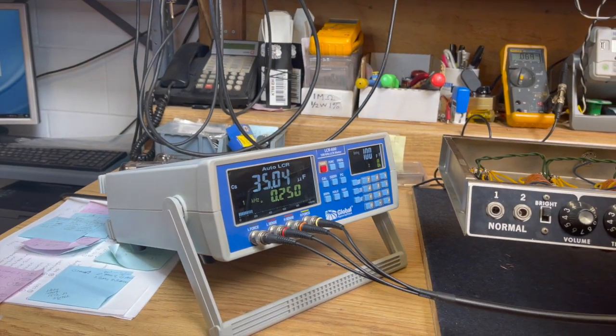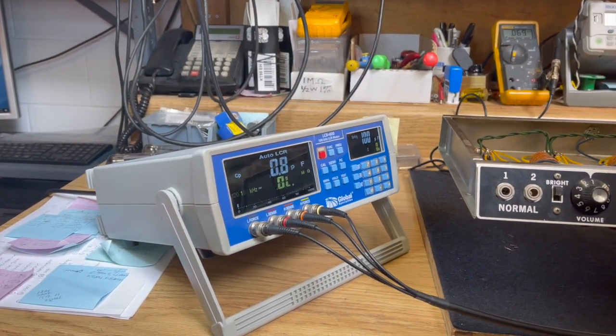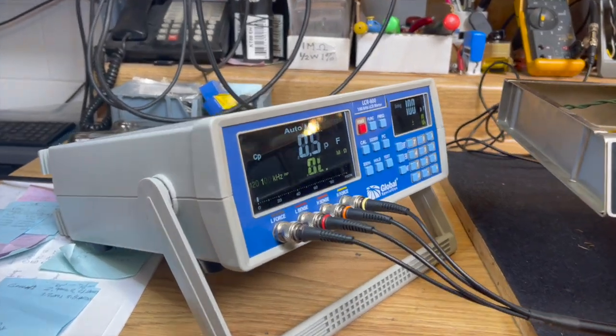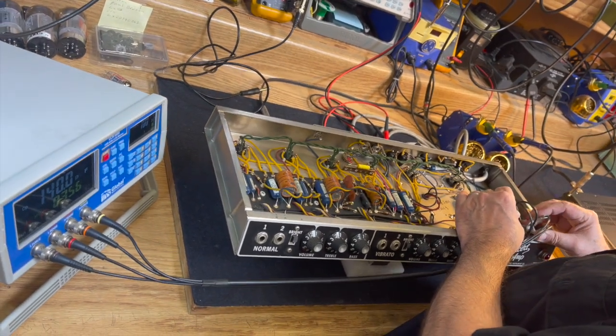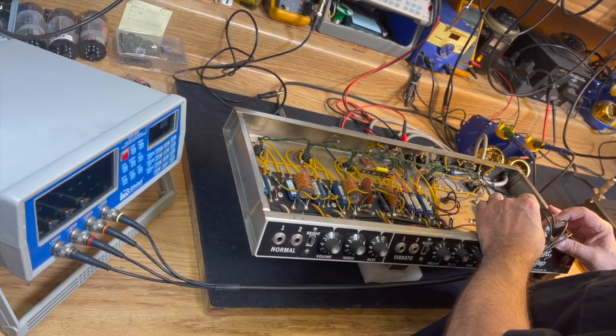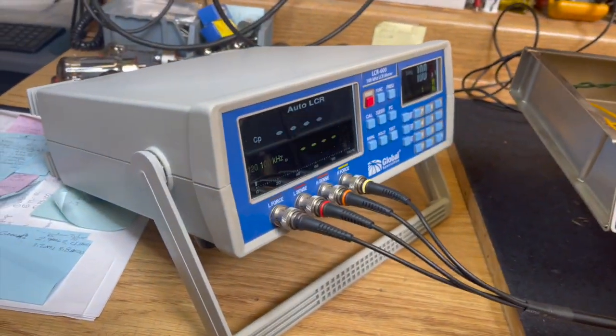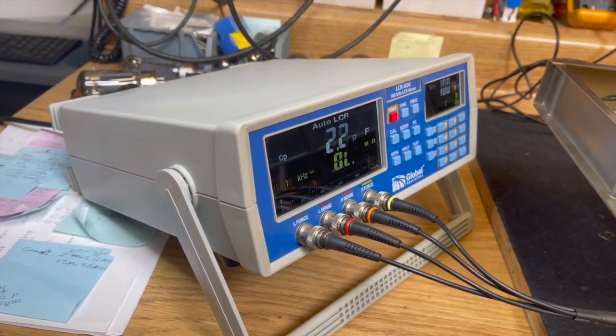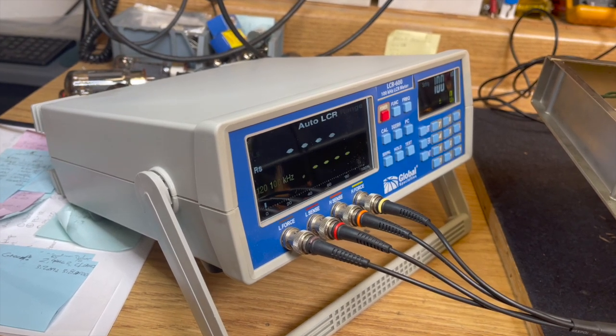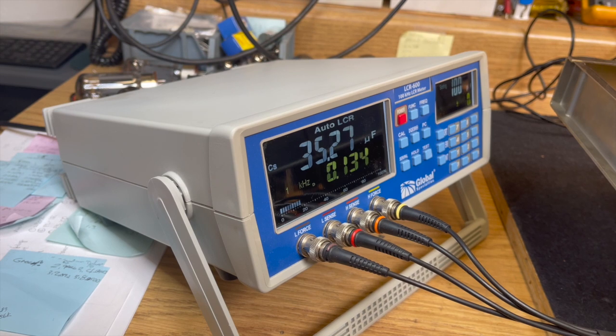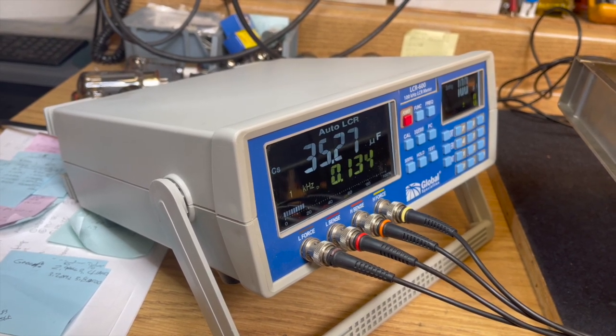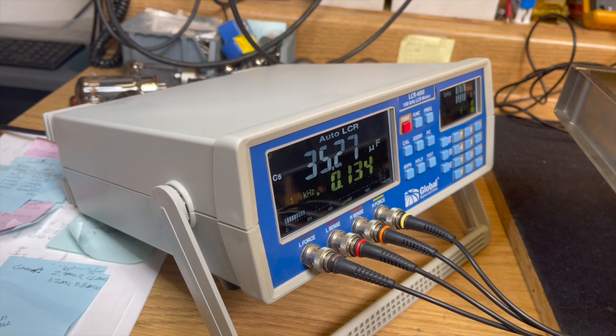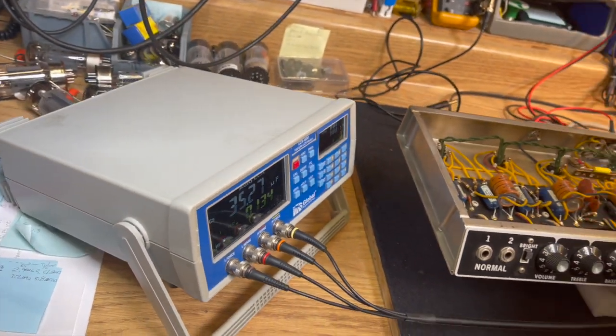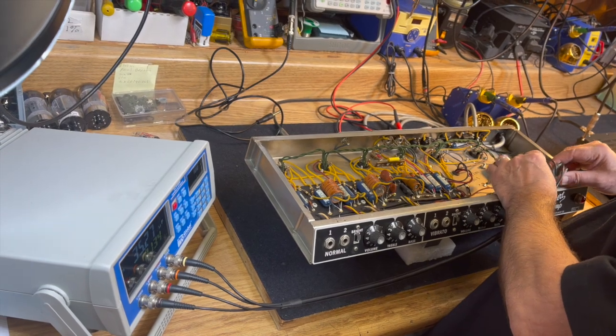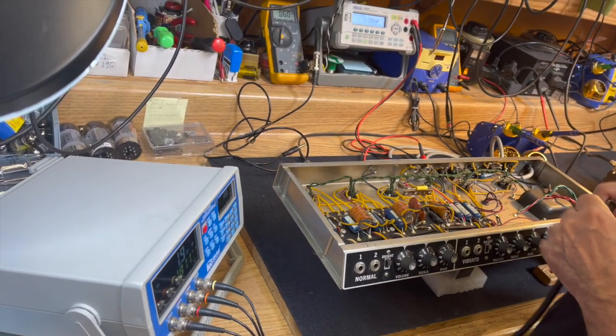So, like I said, it doesn't necessarily have a polarity, and we're going to test that theory by reversing the leads on that capacitor that was reading 35 mics with this meter, and we get the same 35.25 mics that we were getting with the probes wired the opposite direction. So this is giving us a more accurate in-circuit assessment of what the capacitors are doing.